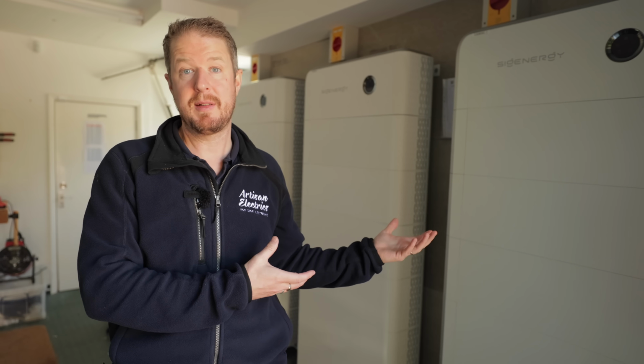Now, why might you want to lower the size of the inverters? Well, it might be to do with the DNO application. So whenever we have to install a system like this, we have to do what's called a G99 application to connect the system to the grid. And sometimes the DNO, distribution network operator, like UK Power Networks or others throughout the UK, will come back and say, oh, your maximum inverter size that you can fit at this property is X amount.